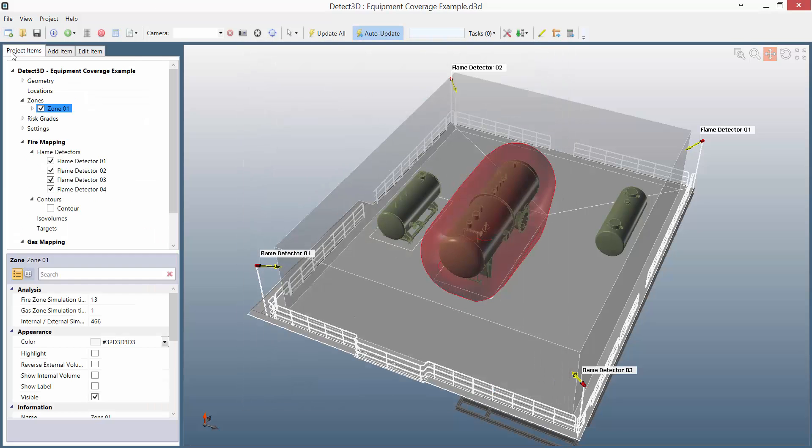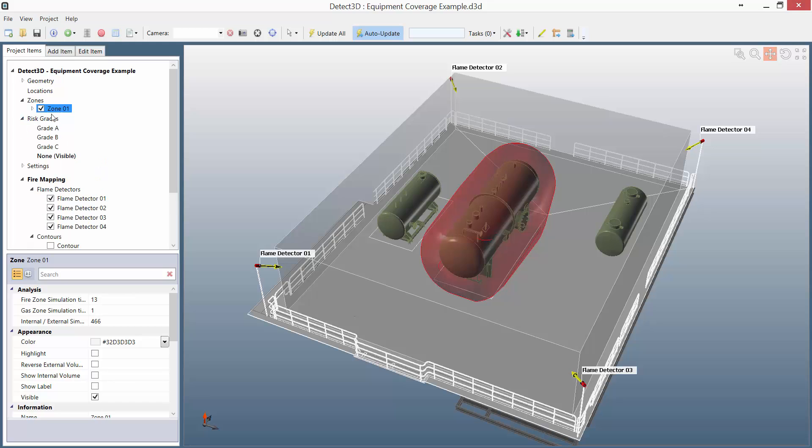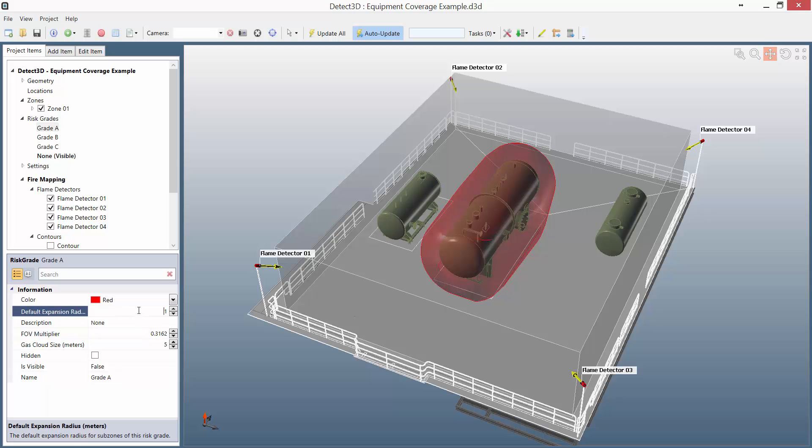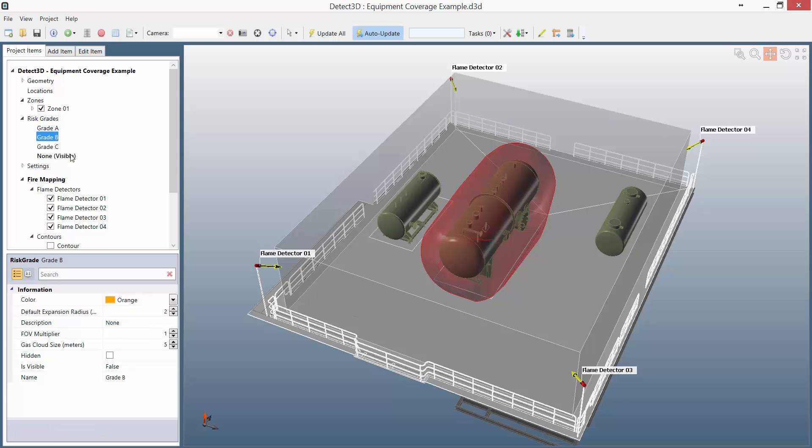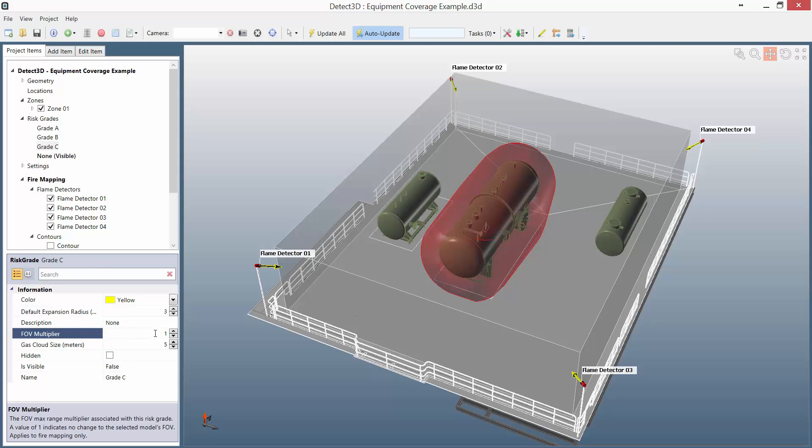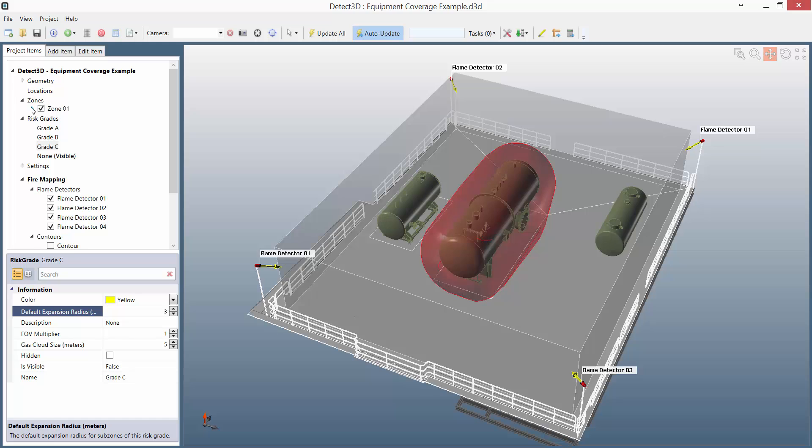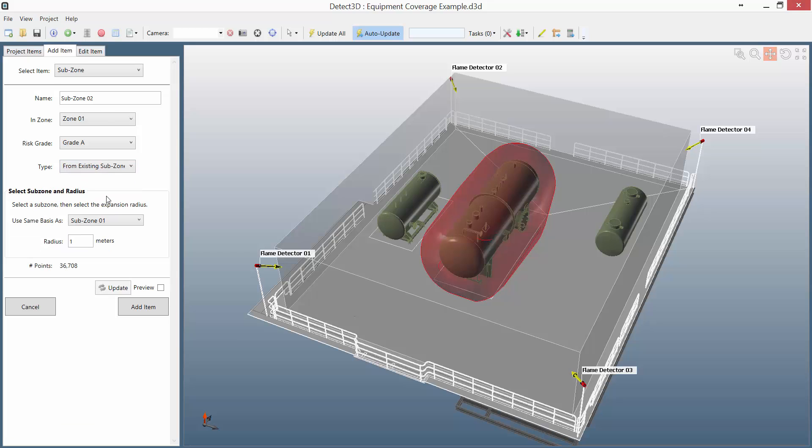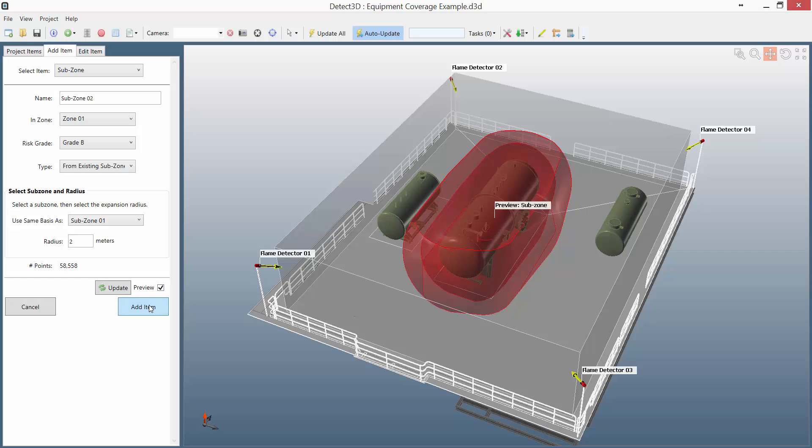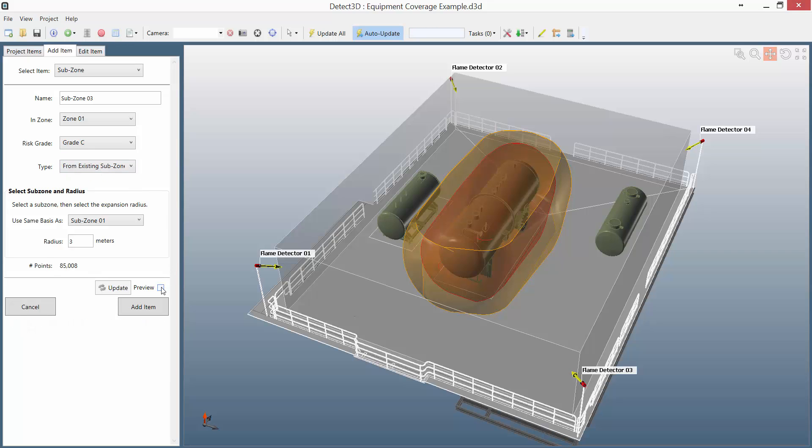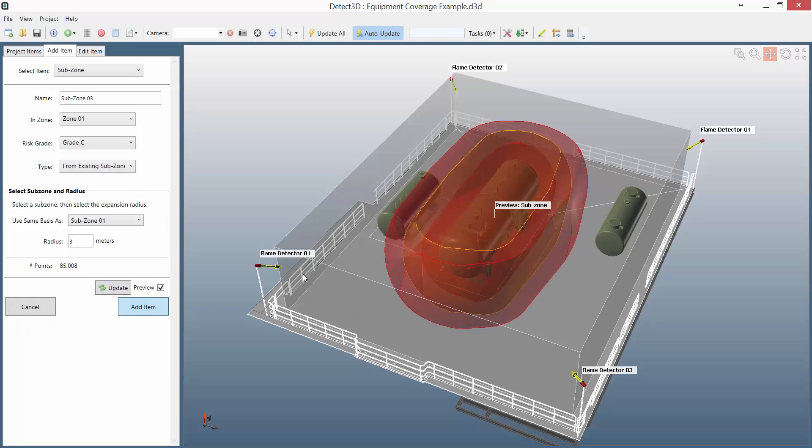I'm now going to extend this method, and just as I set up risk grade A for a 1kW fire at 1m away from the equipment, I'm going to set up risk grade B for a 5kW fire, which is a multiplier of 0.707. I'm going to set that up to be 2m away from the equipment. And risk grade C, I'm going to keep it multiplier of 1 for a 10kW fire, and set that at a radius of 3m. Setting up the new subzones is now really easy. I can use the previously defined subzone as a base. Simply add one at grade B, notice how it defaulted to 2m, and set up another one at grade C, again this time defaulting to 3m. You can just add that to the project.